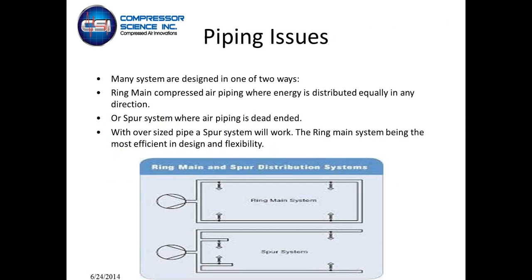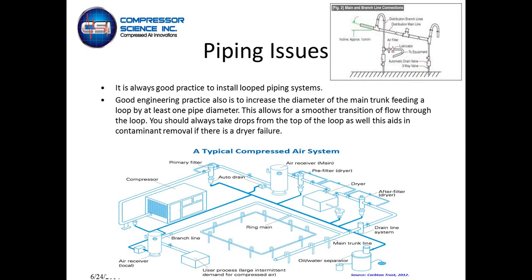Piping issues: systems we walk into are designed one of two ways. They're either ring main, where they're looped in the plant, or they're a spur system where the piping is dead-ended. Spur systems will work, providing that they're sized properly and they have sufficient storage out there to deal with the events in the plant. Obviously, the most efficient is a ring main system, where energy can be distributed from both sides. It's going around whatever way the demand is. It doesn't really matter because it goes both directions.